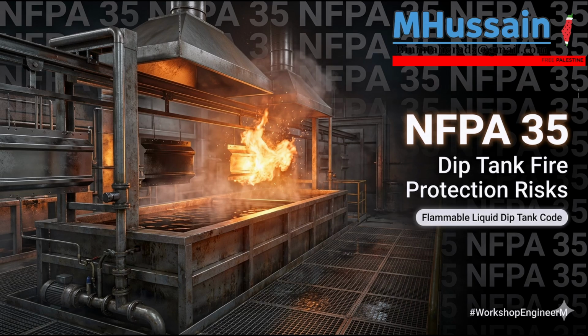Entirely. And that physical reality dictates where you can even place the building in the first place. When you look at the facility layout rules, the standard is enforcing radical isolation. Radical is the right word. Right. Because, first off, organic coating manufacturing operations cannot be located in the same building with other occupancies. You can't just put a resin cooking operation on the ground floor of a mixed-use industrial park with, like, a paper goods warehouse or a commercial bakery next door. Yeah, no, the risk of collateral damage is simply too great. The standard allows for incidental operations, like maybe a small administrative office directly connected to the manufacturing process. But true independent occupancies are completely banned. Makes sense. Furthermore, the building must be accessible from at least two sides for firefighting and emergency operations. You cannot wedge these facilities into tight urban alleyways.